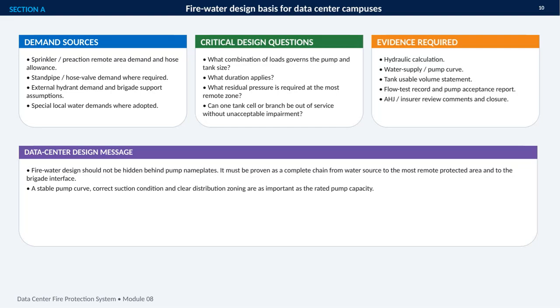This section establishes the fire water design basis for data center campuses. The starting point is to identify every demand source that could operate during an event, including sprinkler or pre-action remote area demand, hose allowance, standpipe or hose valve demand, external hydrants, brigade support, and any special local water requirements. From there, the critical design questions are practical and consequential.